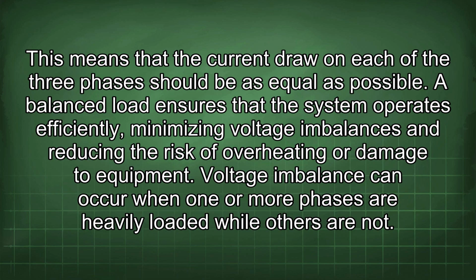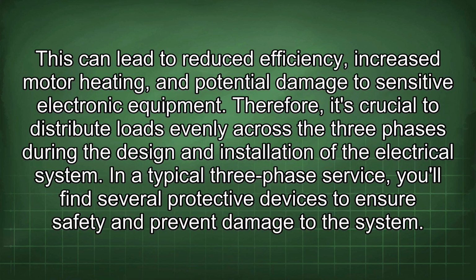This means that the current draw on each of the three phases should be as equal as possible. A balanced load ensures that the system operates efficiently, minimizing voltage imbalances and reducing the risk of overheating or damage to equipment. Voltage imbalance can occur when one or more phases are heavily loaded while others are not. This can lead to reduced efficiency, increased motor heating, and potential damage to sensitive electronic equipment. Therefore, it's crucial to distribute loads evenly across the three phases during the design and installation of the electrical system.